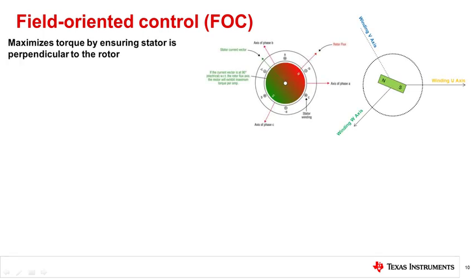Finally, the last control method is field-oriented control, or FOC. FOC is a PWM modulation technique that maximizes the torque in the motor by controlling the stator current so that it is always perpendicular to the rotor flux.